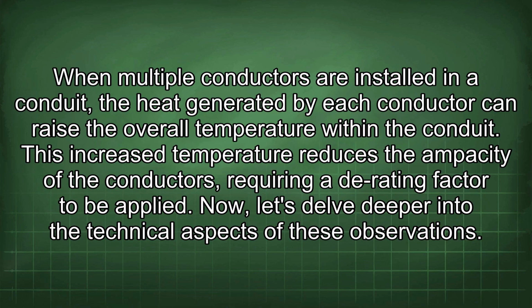When multiple conductors are installed in a conduit, the heat generated by each conductor can raise the overall temperature within the conduit. This increased temperature reduces the ampacity of the conductors, requiring a derating factor to be applied. Now let's delve deeper into the technical aspects of these observations.